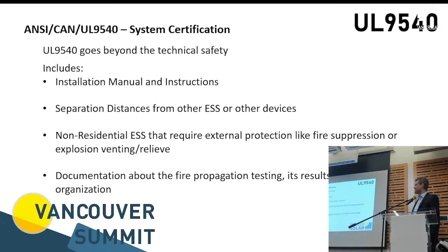And at the end of the day, you also have to deliver to your inspector the actual documentation, what went into that system certification. So, for example, if you use a battery system, for example, from Pylontech, Pylontech has specific documentation for the UL 9540A, the fire propagation testing. And if you issue all the documentation to your inspector with a certification document, that is part of that overall certification.